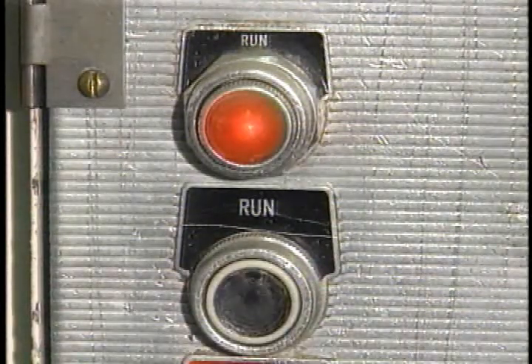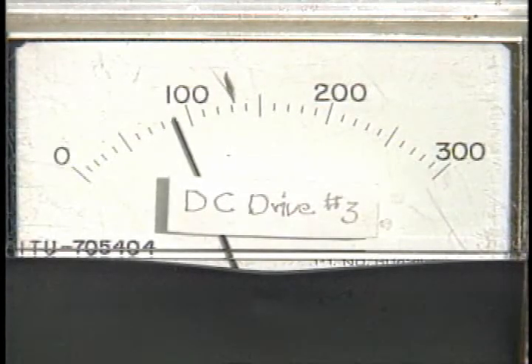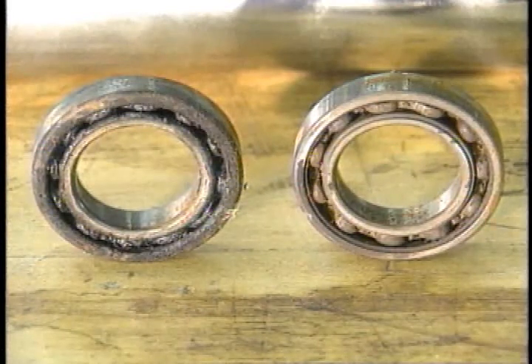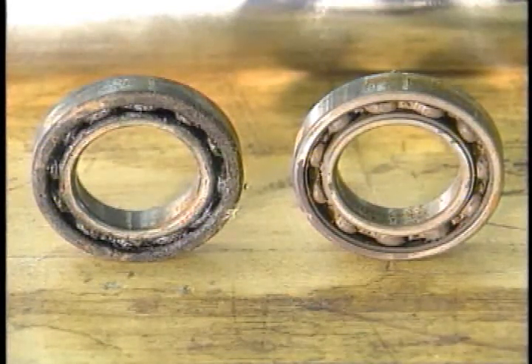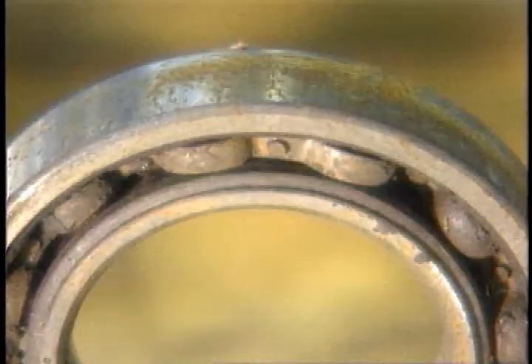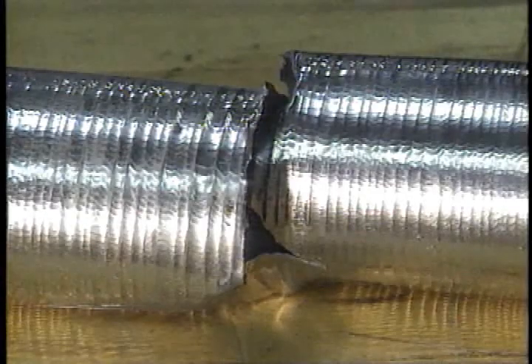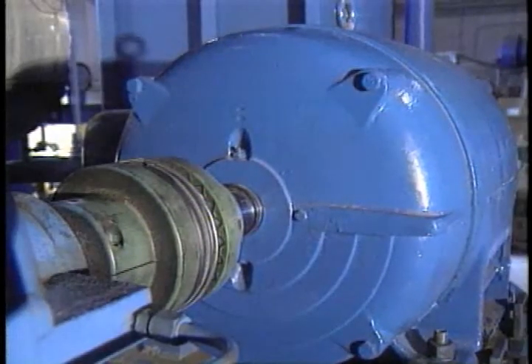If the shafts are even slightly out of line, energy consumption can increase dramatically, especially if the equipment operates under heavy load. If the degree of misalignment is more severe, however, destructive forces may be placed on the bearings, seals, and shafts of both the drive unit and the driven unit, and on the coupling which links them.